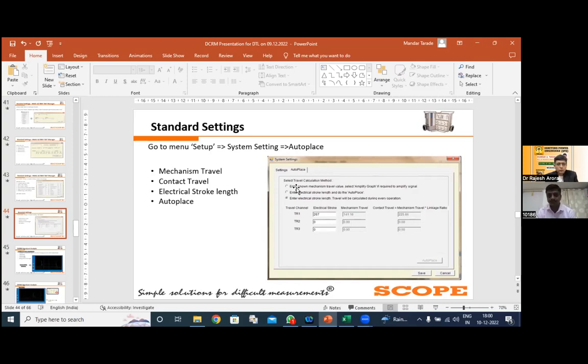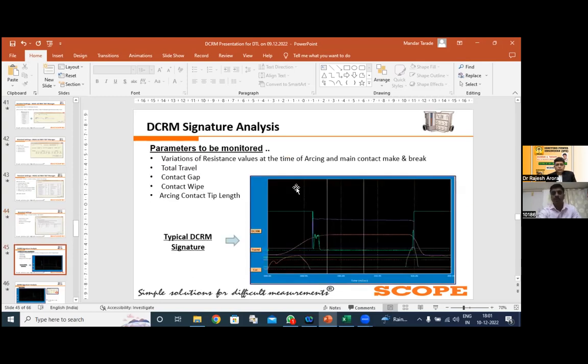So please continue. I already highlighted why feeding the electrical stroke length is important, irrespective of any instrument you are using for health assessment of the circuit breaker. The placement of the transducer, feeding of the electrical stroke length and the linkage ratio, as well as the velocity point are very, very, very important. By taking the reference of these points only, any instrument in the world does the entire calculation, and accordingly you get the mechanism travel, contact travel, default velocity, and the return velocity. So feeding the important points and setting the parameters right plays a very significant role.